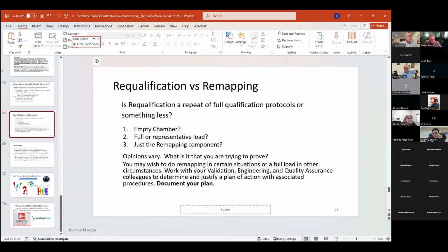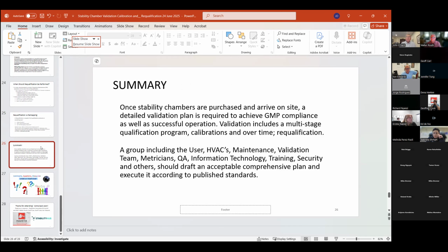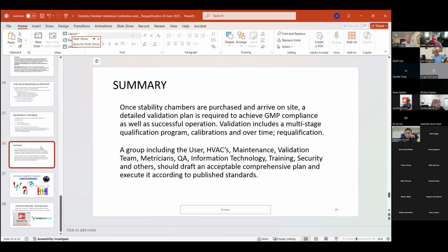Okay, we are reaching the last few minutes of our program time here. Let's sum up a bit and say once stability chambers are purchased and arrive on a site, a detailed validation plan is required to achieve GMP compliance, as well as successful operation. Validation includes a multi-stage qualification program, calibrations, and over time requalification. A group including the user, HVAC, maintenance, validation team, metricians, QA, information technology, training, security, and others should draft an acceptable, comprehensive plan and execute it according to published standards. And that's really good coverage in order to give yourself the best outcome possible when inspectors come into the room.